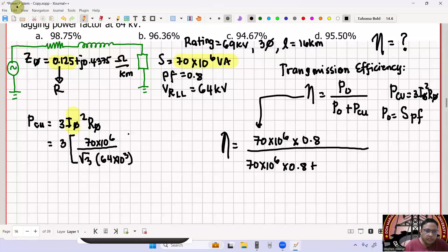So this quantity squared times R per phase, which is 0.125, but this is in ohm per kilometer. So what do we do with the ohm per kilometer? We multiply it by the length, which is 16 kilometers. So therefore PCU now is equal to 3 times 70 mega over square root of 3 multiplied by 64 kilo, the quantity squared, times 0.125 times 16, canceling the kilometers. So therefore this is now...